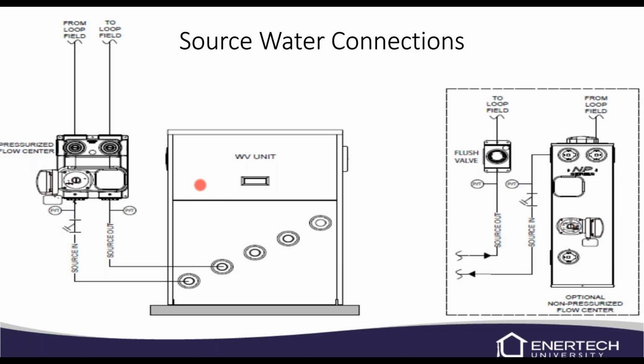Now, just because the WV unit will tell you your water flow, I would still recommend that we install pressure temperature ports. That way we can confirm if those sensors and thermistors are reading properly, because those could always be the problem. So make sure you're always installing pressure temperature ports.